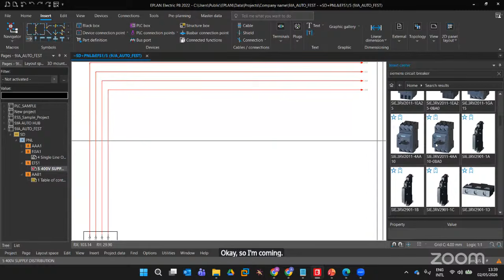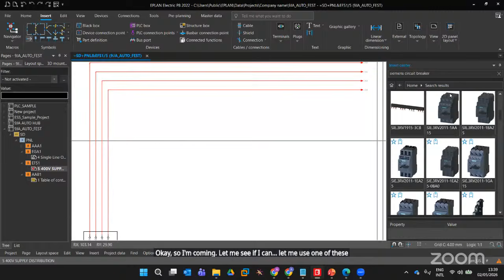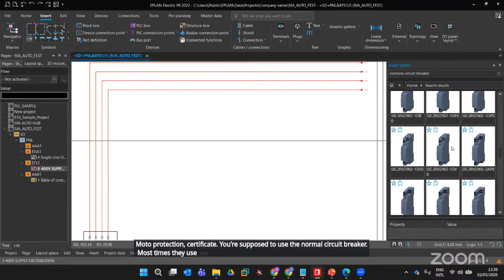So I'm coming. Let me see if I can. Let me use one of these motor protection circuit breakers. You're supposed to use a normal circuit breaker. Most times they use motor protection, or they can use a contactor then use motor protection. You have contactor, you have overload, then you have a motor. So the overload is checking for the heat that the motor is drawing. If it's overheating, then it goes off.